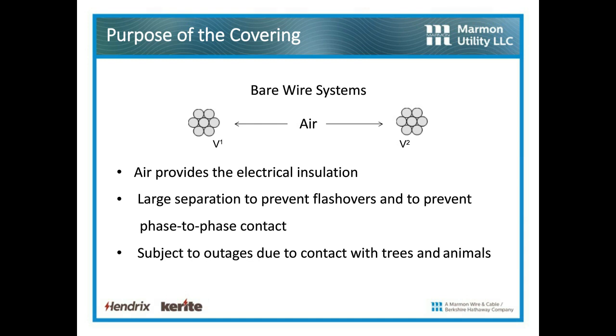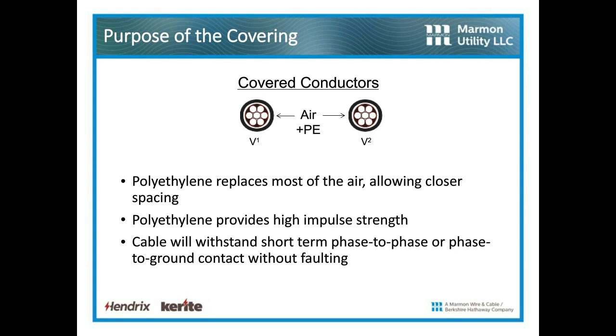So what we do is we put some polyethylene on those bare conductors, and that polyethylene as an insulator replaces most of the air and allows us to bring those phase conductors closer together. That polyethylene gives us a high BIL, gives us a high 60 Hertz withstand, and now those phase conductors are able to withstand short-term phase-to-phase contact, phase-to-ground contact, phase to what have you, trees, animals, et cetera, without suffering a fault.